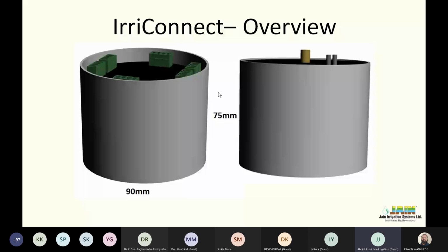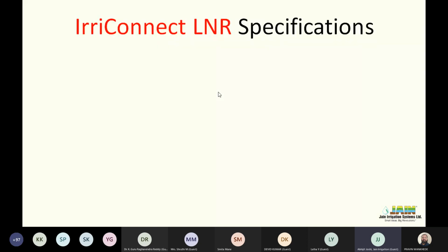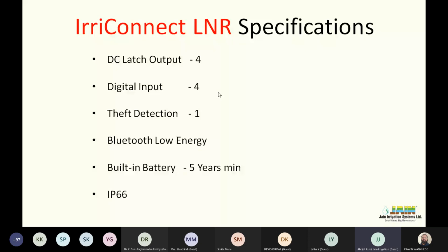In a farmer's field, some farmer will always try to steal the water. They learn how to open up the valve manually by pulling out the tubing or similar. If there is no schedule for the valve and the magnetic switch sends a signal converting from NO to NC, the RTU will immediately recognize that water is going through the valve without any schedule, meaning water theft is happening. It immediately generates an alarm, and a person can then access that field to observe what is happening there.